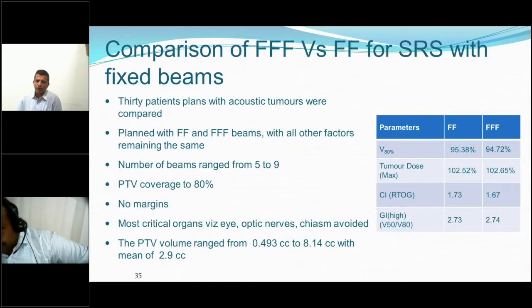See, actually I said that when you use FFF beams, the surface dose is larger for narrow beams. But when you go for larger linear accelerator beams, where the scatter overtakes that, the surface dose is not a major contribution because of FFF. When you go for a smaller field size, because of the softer component of FFF, the surface dose is higher. But when you go for a larger field size, it's not there. Right, so that's what I actually mentioned.